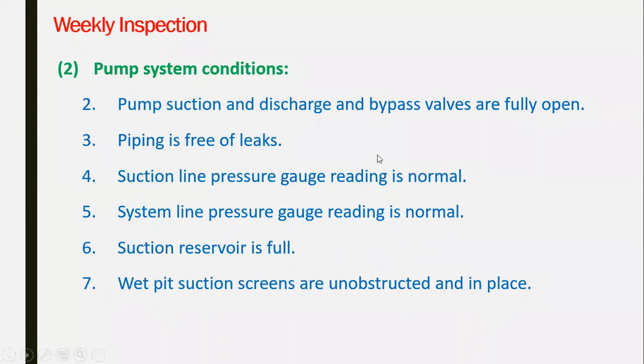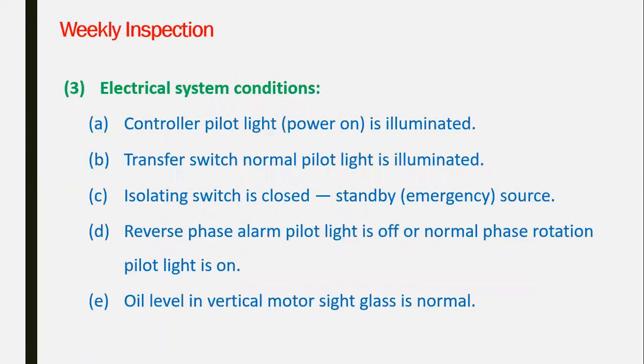The piping is free of leaks. Suction line pressure gauge reading is normal. System line pressure gauge reading is normal. Suction reservoir is full; the suction reservoir is the water tank. The wet pit suction screens are unobstructed and in place. It is all visual inspection. So this is a visual inspection.